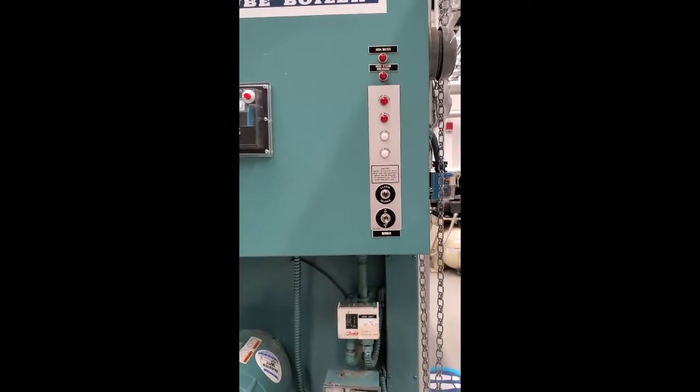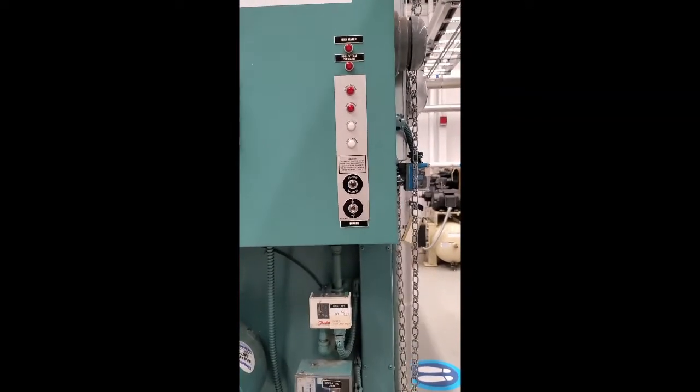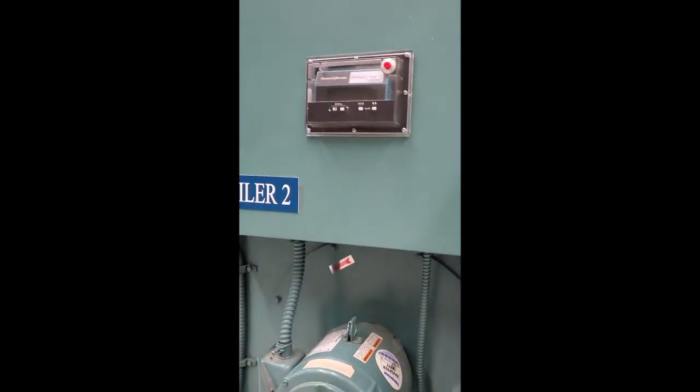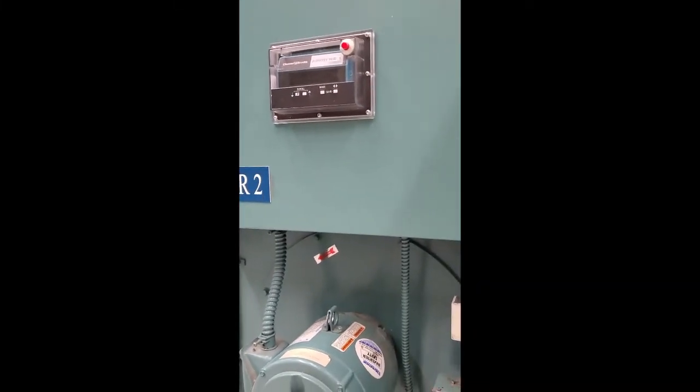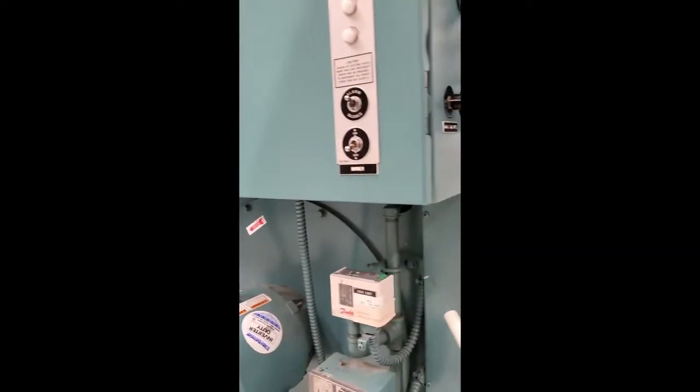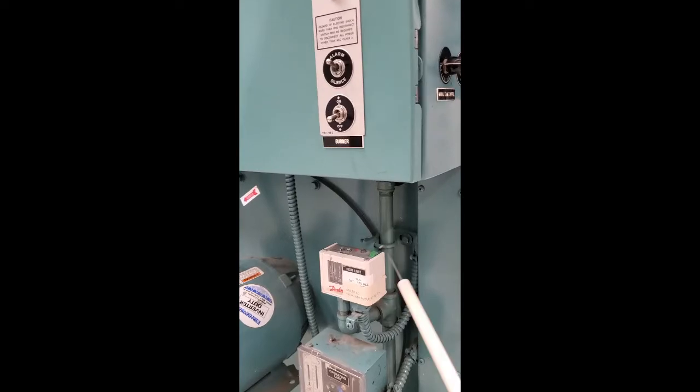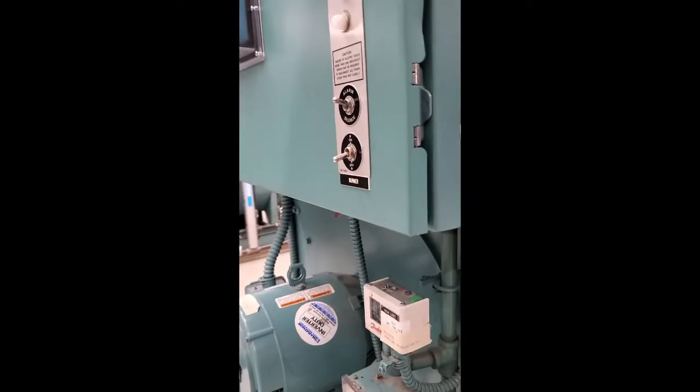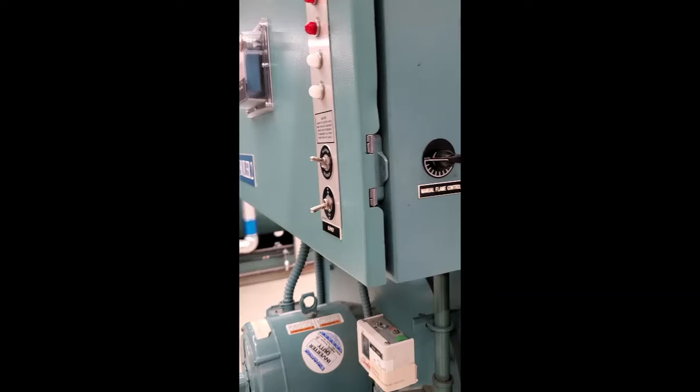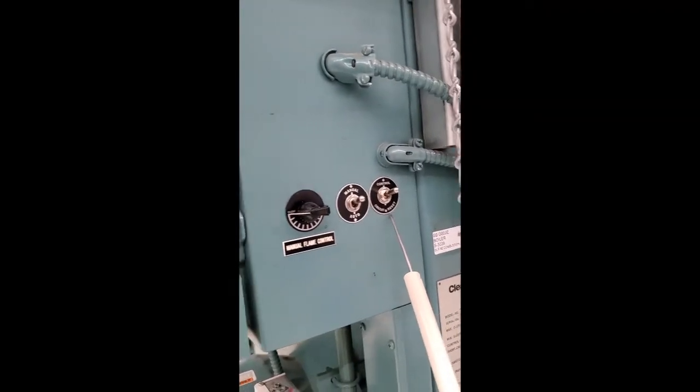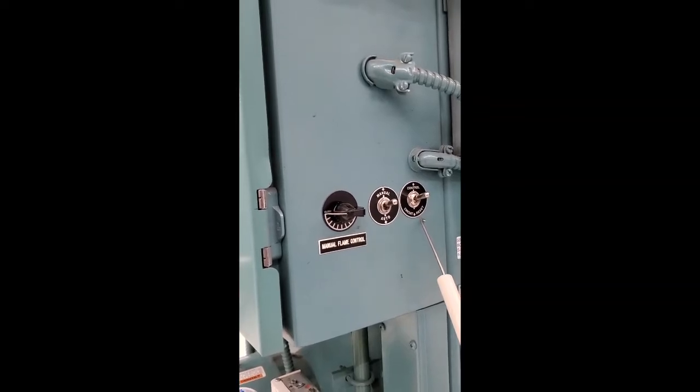On the programmer itself, you have a reset right there. On the high limit pressure cutout, there's a reset there. And on the control circuit here, you have to enter the reset. Any one of these, if they are not reset, then you cannot start the boiler.